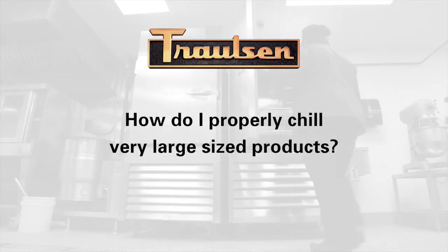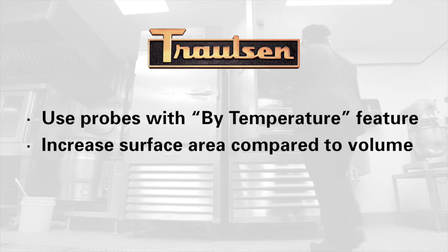How do I properly chill very large size products? Large products are best chilled with probes using the by-temp feature. However, some large products will be too large to chill safely within FDA guidelines. In this case, it is necessary to reduce the individual size of the products in order to allow them to chill quicker. Surface area to volume ratio has a direct correlation to chill times. Increasing the surface area relative to the total volume will in turn reduce the product chill time.